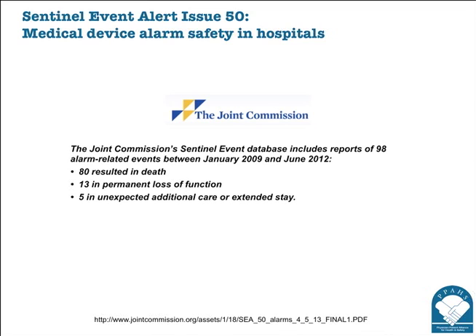Note that we train ourselves to listen for specific alarm sounds because manufacturers have learned over time you cannot have one alarm sound for every condition. For us, our ventilators have three separate alarms, and when we hear that one specific alarm, we know to drop whatever we're doing to find out what's going on. But that can't be said for all devices.